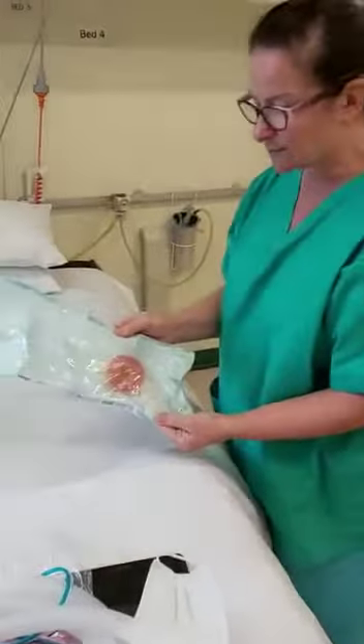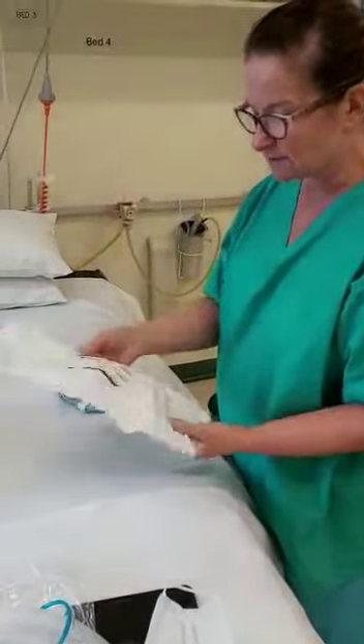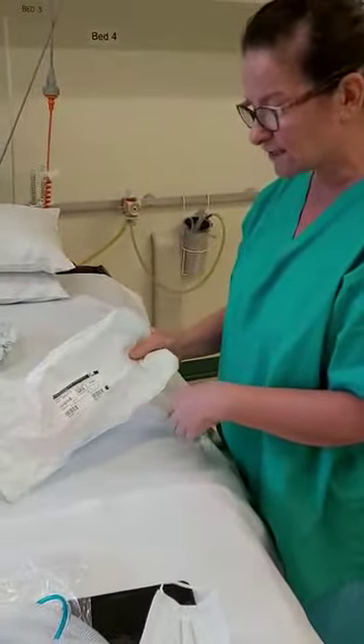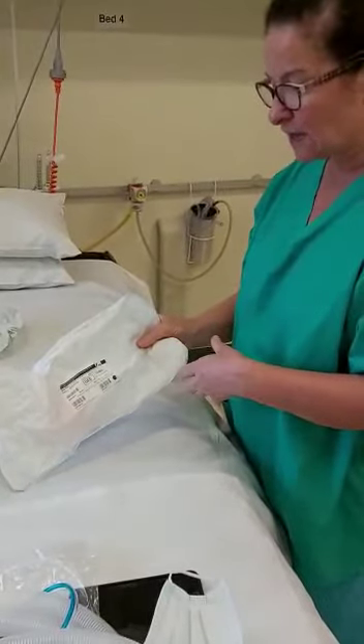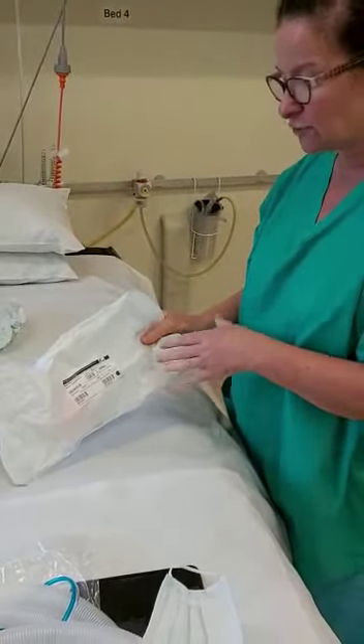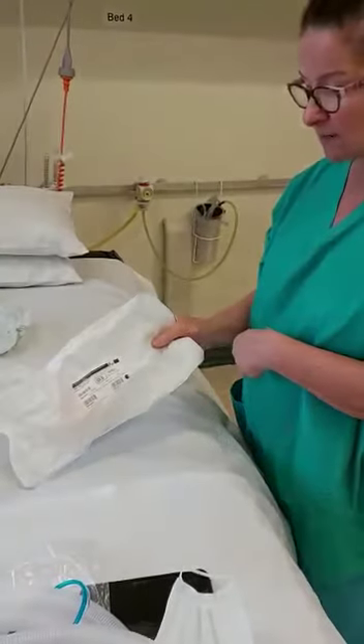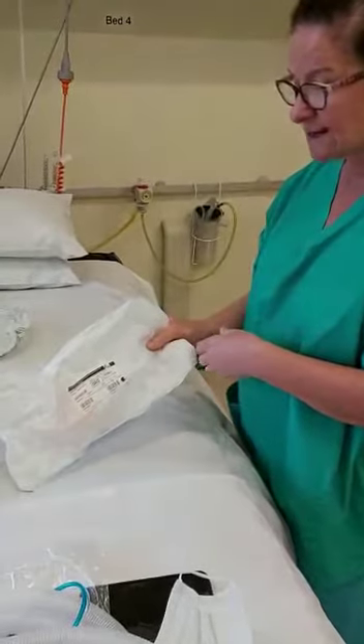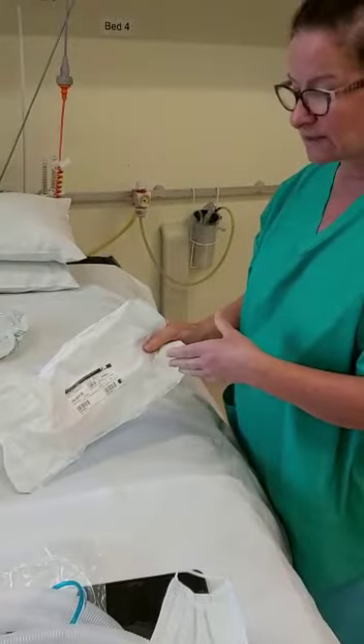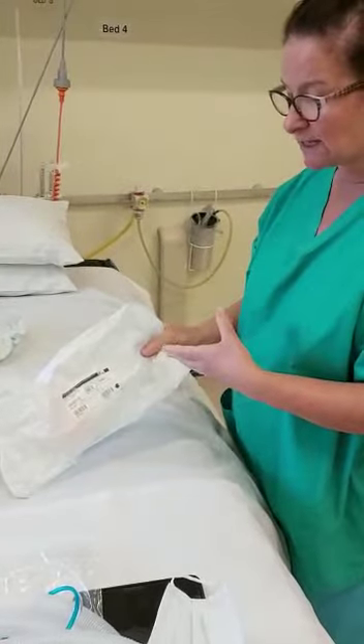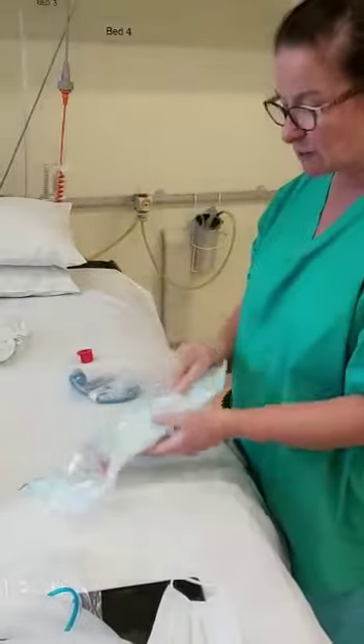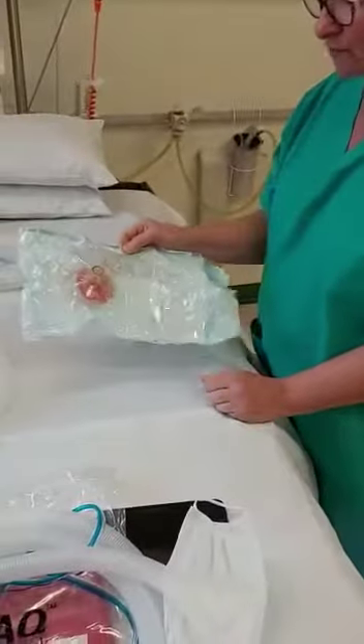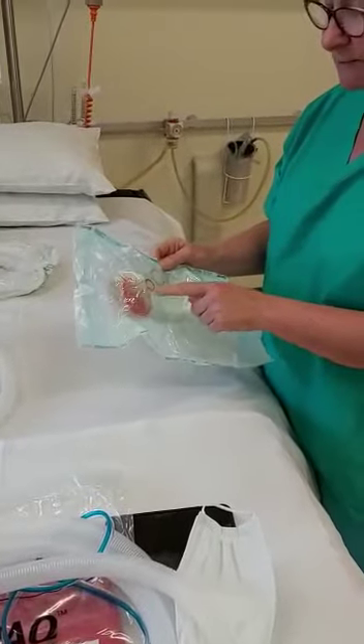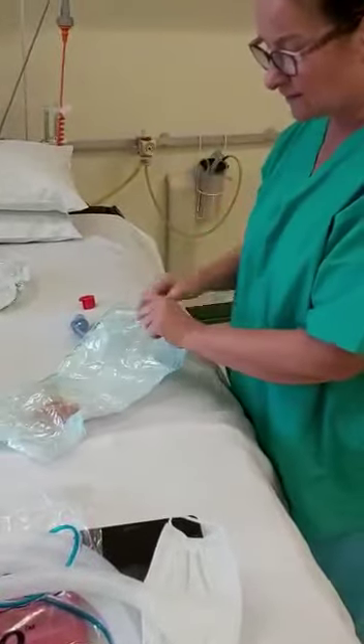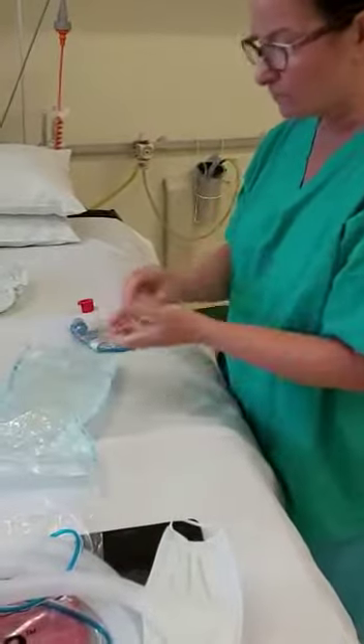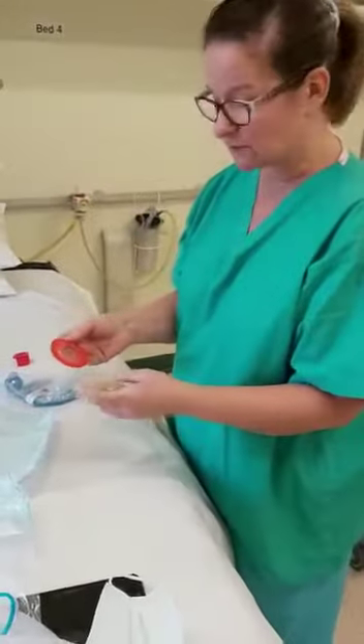So that's your tubing out of the packet. You'll also need an expiratory valve. The expiratory valves come in a packet with a traceability sticker on the back, and once you've put the expiratory valve onto the ventilator, you must keep this packet. It goes in a clear plastic wallet on the side of the ventilator, and that will be used once the ventilator is dirty and no longer needed, because we need to autoclave these parts. So these are the only bits that are autoclaved, and it's your expiratory valve, which is amber coloured, and then the little red diaphragm, which both of these need to be autoclaved after use.